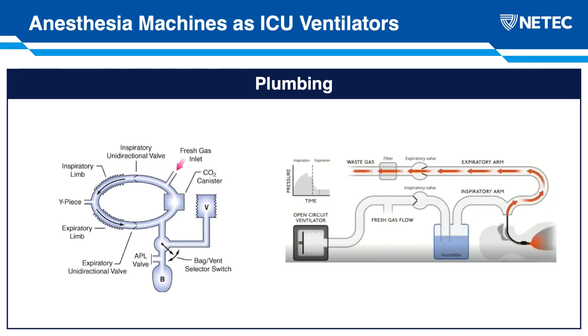But this is where it's different. It can pass through a CO2 canister or a CO2 absorber, have the CO2 scrubbed out of the exhaled gas, and then be mixed with the fresh gas again. And in this way, a patient can rebreathe.